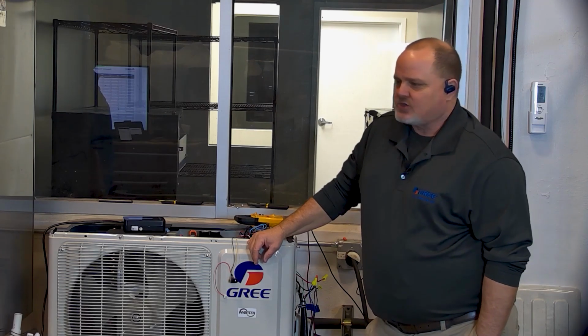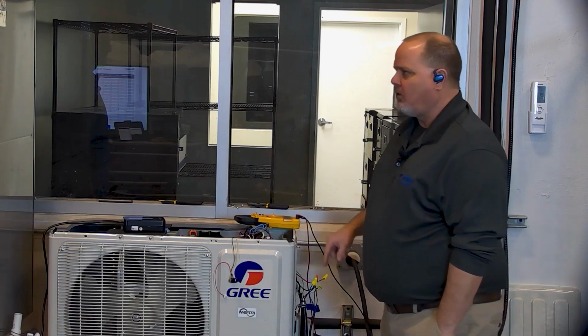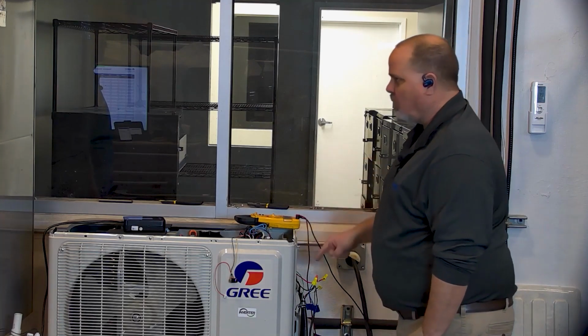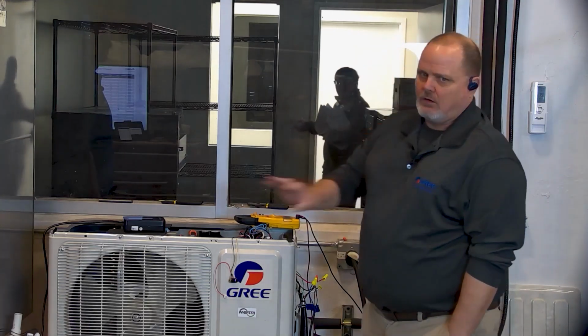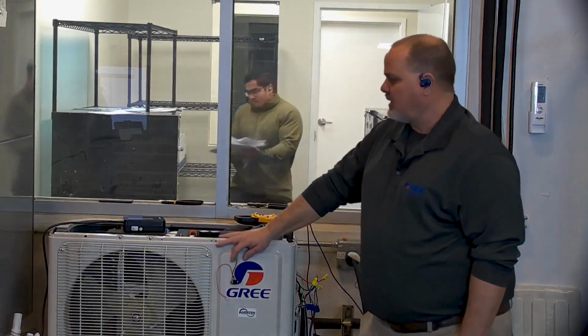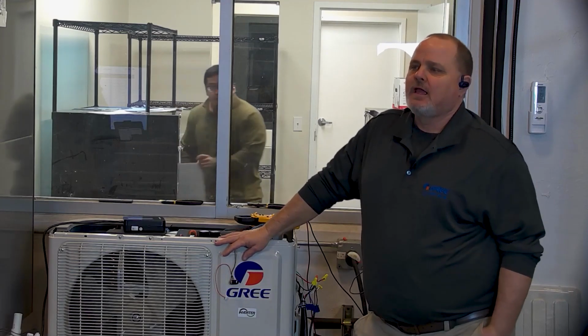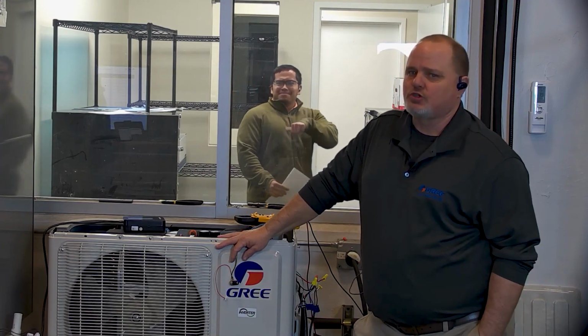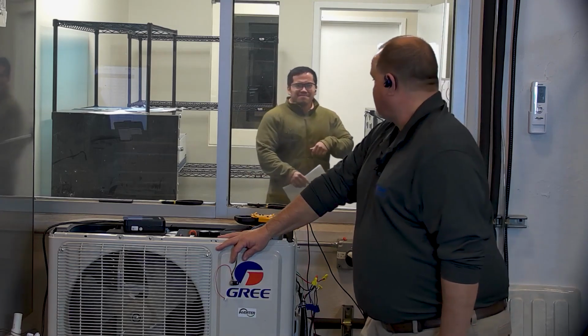So I can't stress enough, a solid cable, 14-4 stranded cable, 1 wire from outdoor to indoor, no interruptions in between it. The only time that it's acceptable to have an interruption there is if the code requires you to have a disconnect inside, meaning it has to have a 3-pole disconnect. Some localities require you have a 3-pole disconnect on the indoor unit. You got no way around that. And if it's required, you're going to have to put it in there. Make sure it's a 3-pole. You got to break 1, 2, and 3 going to the indoor unit.